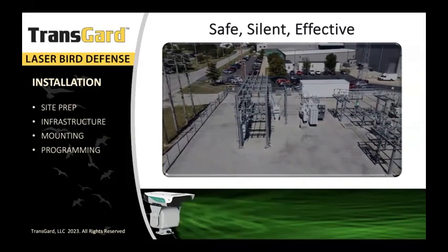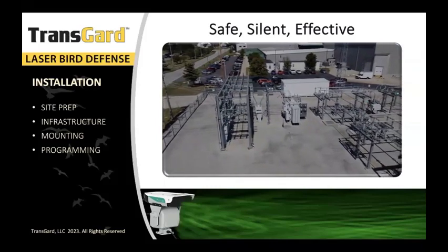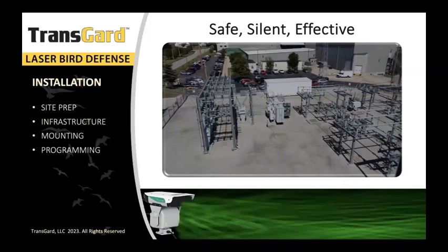And the reason I like this little short video that we're showing here is because we keep the laser confined to the boundaries of the substation. The big question that comes up is, does the public see it? Or in the case of here, we have a parking lot right next to it. No, the laser is actually bouncing inside of the substation off of the equipment. And you can see it's got very specific targeted points. The software is designed to halt the laser should it deviate from its programming, where the next waypoint is not followed, the laser would shut itself down because we do not want it to point outside of a substation or just randomly go on its own.